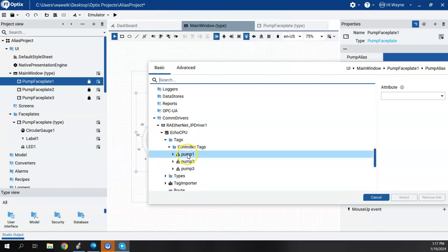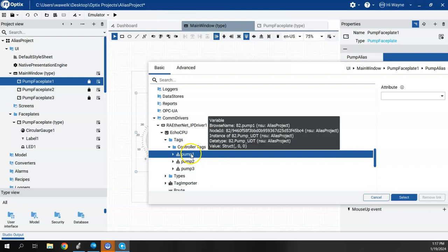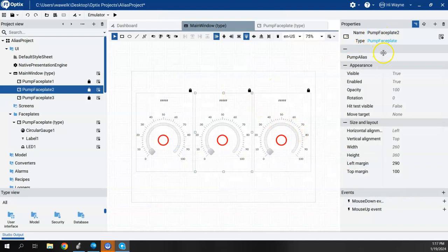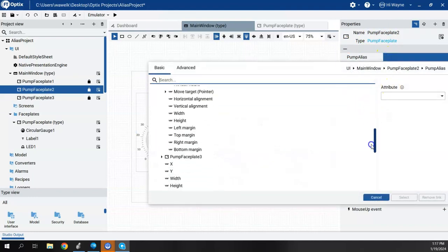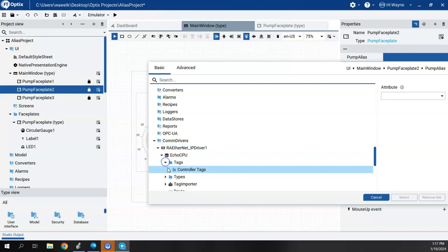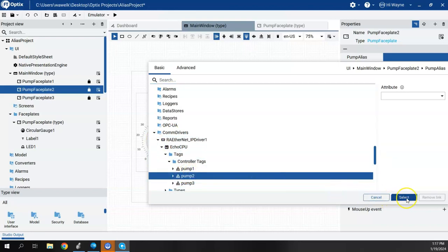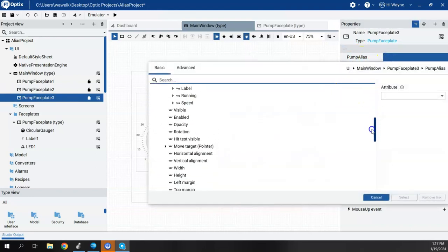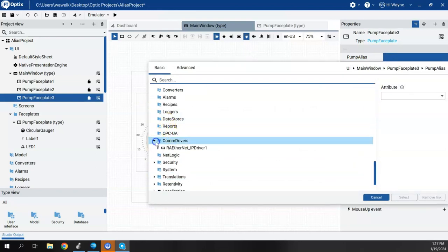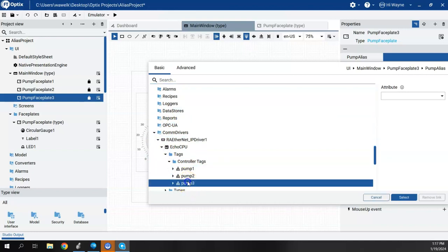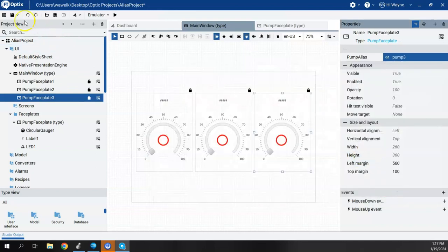All I have to do now is assign the UDT instances to each faceplate. For Pump Faceplate One, I go to its Pump Alias property, set the alias to Com Drivers > Tags > Controller Tags > Pump One. For Pump Faceplate Two, I assign it to Pump Two. For Pump Faceplate Three, I assign it to Pump Three. Then I save.